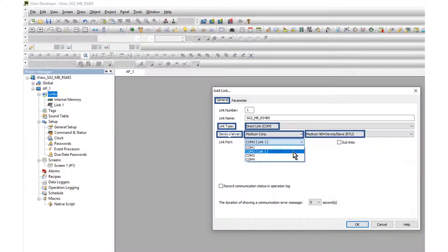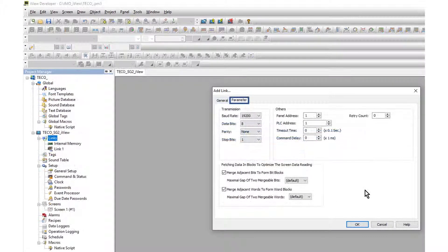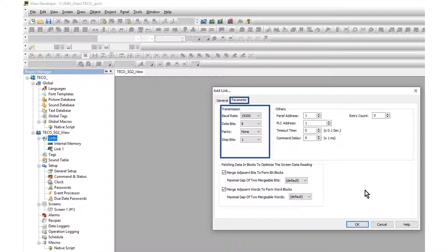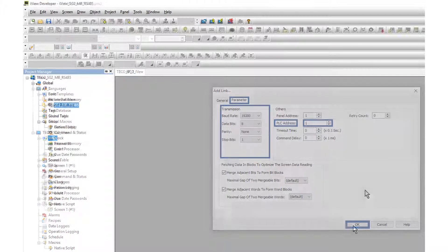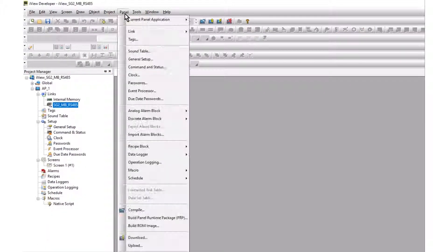The RS-485 link is COM2 for this hardware. Open the Parameter tab. The transmission parameters must match the SG-2 parameters. The PLC address is set at 1, which is the ID set in the SG-2. Click OK, then compile and download the project.